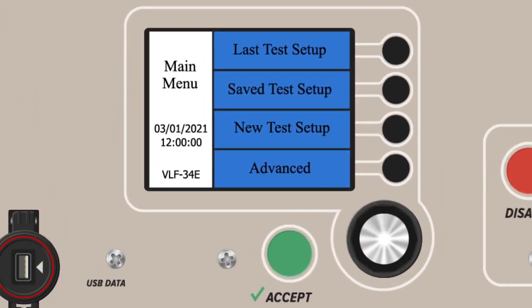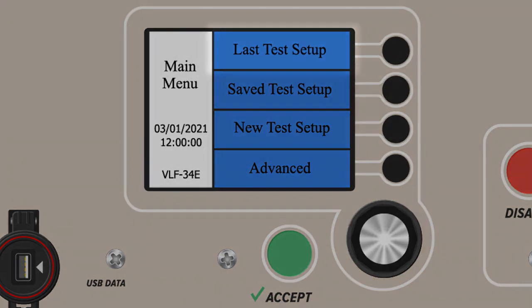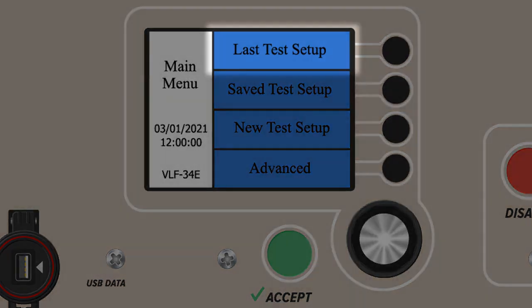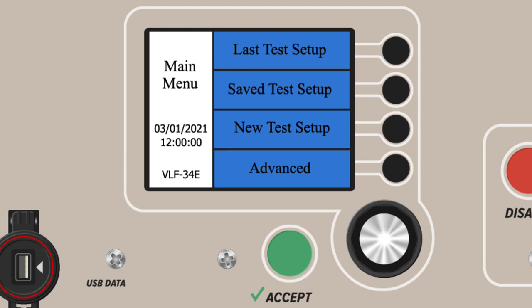Menu operation. Operation of a VLF E-Series is based on a standard structure of menus and submenus, all of which can be controlled with bordering buttons and the rotary encoder. In the main menu, there are 4 major functions to choose from. The first is Last Test Setup. This allows users to automatically run a defined test profile or sequence, specifically the last one used on the device. For many electrical testing professionals who use a small range of consistent tests, this is a useful feature.